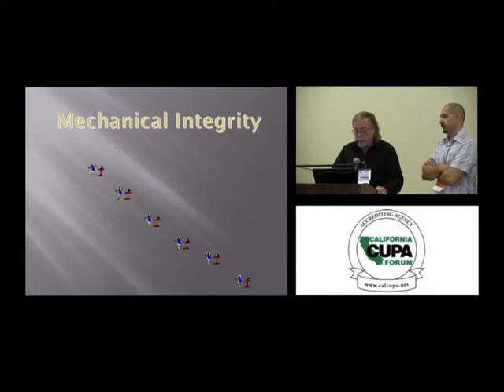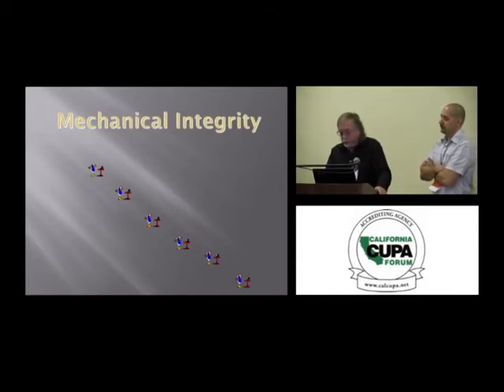And then we drill down to the facility itself and the support system for that facility, such as the engine room or compressor area and the global system. And then we go as far as drilling down to each component, and we find out what they've been doing. Have they checked motor current? Do they have local control? Is it functioning properly? Are they doing things such as vibration analysis, annual alignment on their compressors, checking end play, doing their oil analysis, and so on and so forth. It's quite extensive for each one.